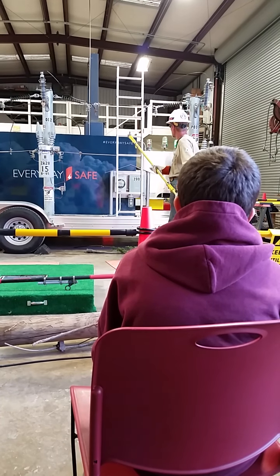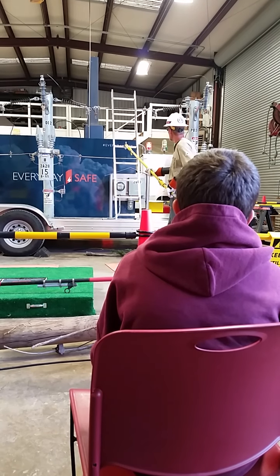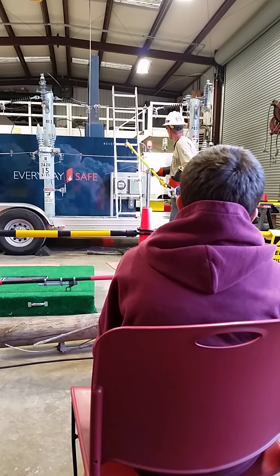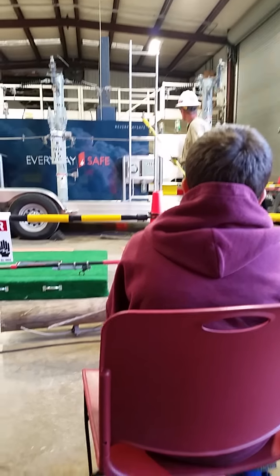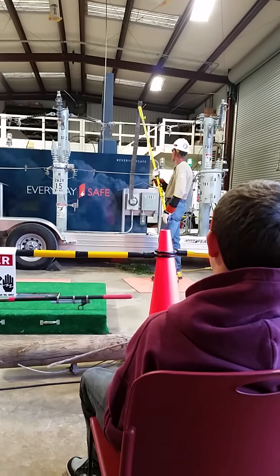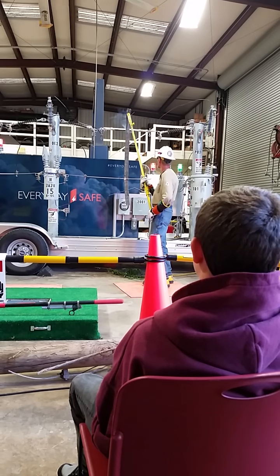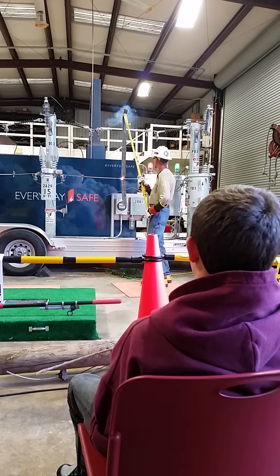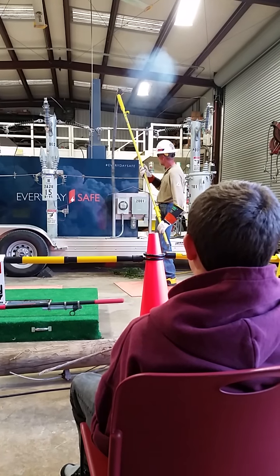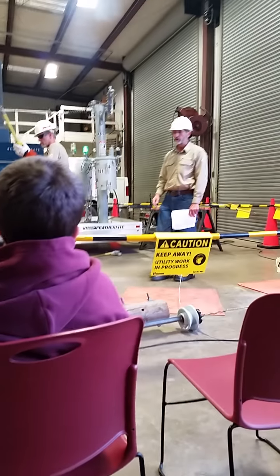When you're ready, Stan. Make it hot. Coming hot. All right, and again, once that arc starts, it's way. Make it hot. Coming hot. And he can sit there and keep that on there and literally set that hose on fire. So just because it's cloth, not a piece of metal, you think, well, that's probably not a conductor. A good dirty water hose is very much a conductor.